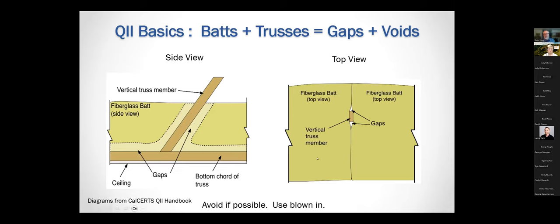And so what happens is you get these voids and gaps in between wherever you have a vertical framing coming up through the fiberglass bats. The bats don't touch all the way around it. And from the top looking down, it just looks like a little triangle. Oh, it's just this little gap right here. But the gap actually goes all the way down and follows all the way through. So there's a lot of places where air gets in and can reduce the R value.